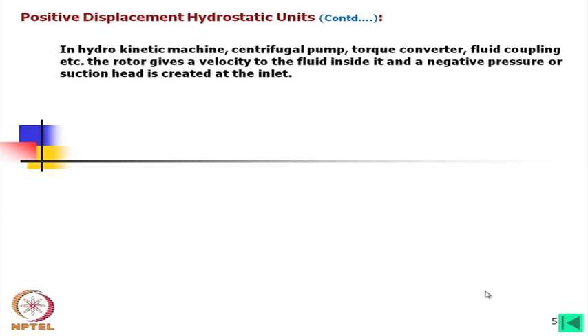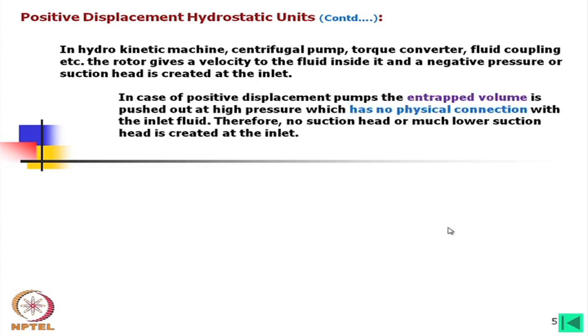In hydro-kinetic machines — centrifugal pumps, torque converters, fluid couplings — the rotor gives velocity to the fluid, creating suction head at the inlet. In positive displacement pumps, the entrapped volume is pushed out at high pressure with no physical connection to the inlet fluid, so no suction head or much lower suction head is created at the inlet.